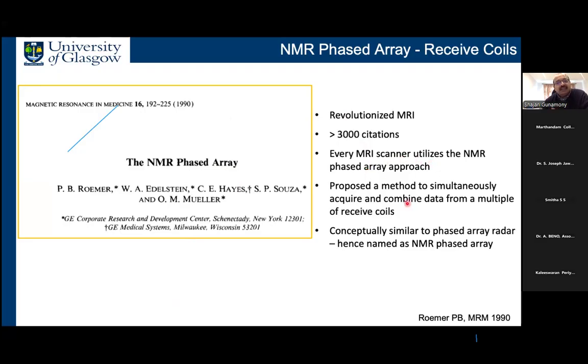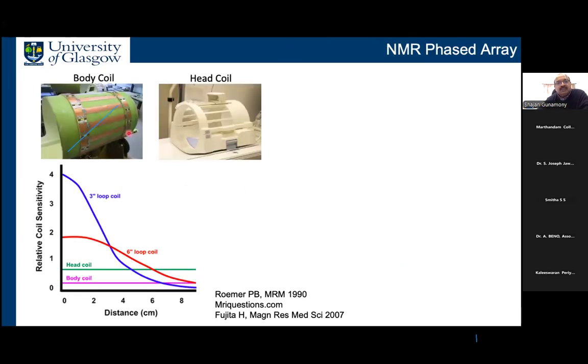So he proposed a method to simultaneously acquire data from multiple small receive coils and combine this data into a single image. And this way you get much more SNR than a birdcage coil. And his concept is very similar to a phased array radar, and hence he named it an NMR phased array. So here you have the birdcage coils, as I showed you earlier.